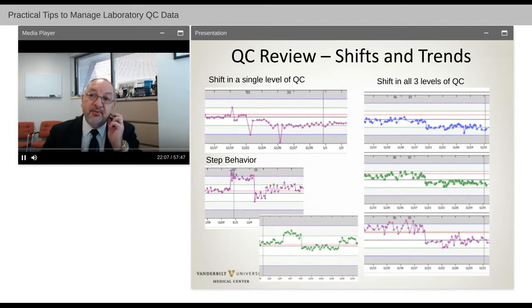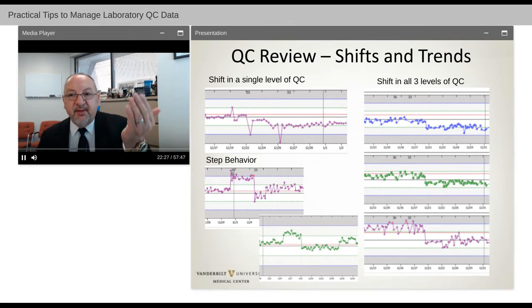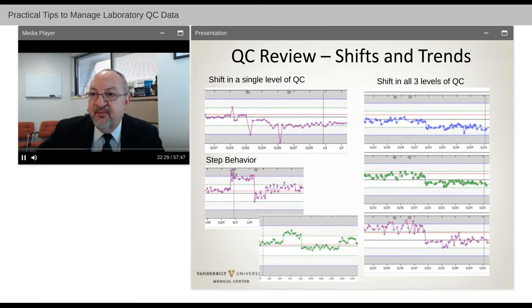As I review through our quality control, I'm looking for shifts in a single level of QC. Here you can see very close to the mean performance at the beginning of the chart, leading to a shift almost 1 SD near the middle of the chart. Step behavior, where we see sudden shifts up and then down in performance, or shifts in all three levels of quality control. Here you can see a decrease in the ranges for all three levels.